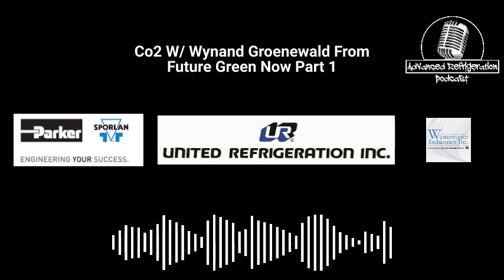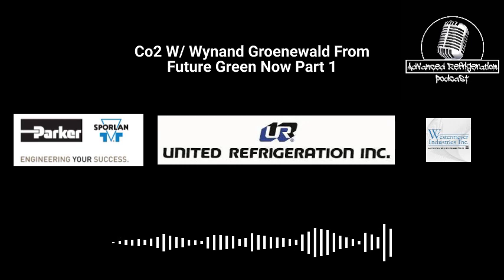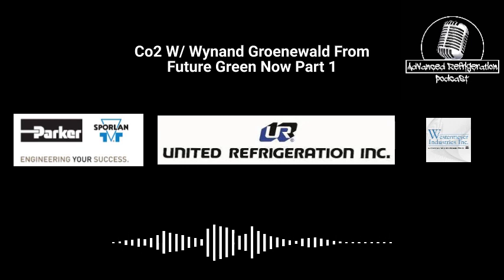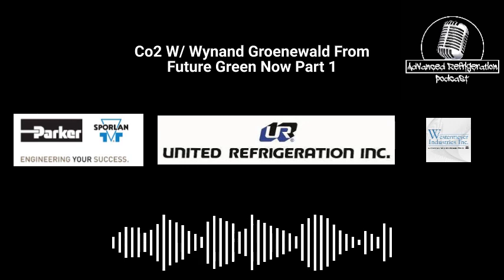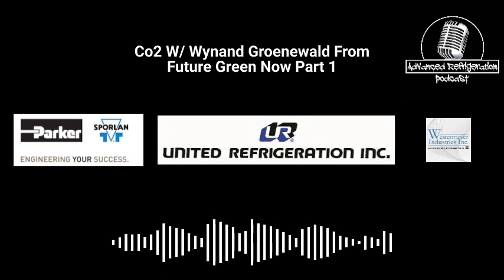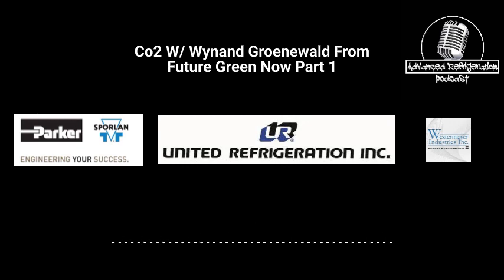No, I don't think so. I can't say particularly. I think the problem that you are describing here is more, like we said, a capacity and condenser size point of view. Even whether you control or whether you drop or whether you on off, if anything is running, then, that's why I say, even if you switch everything off, if there's a slight breeze going over that condenser, you're still over condensing. You're still making it hard for you. The problem is you're making it hard for your system to maintain above its minimum set point.